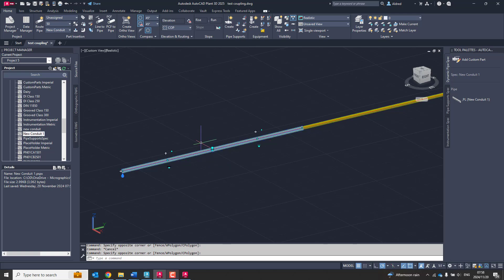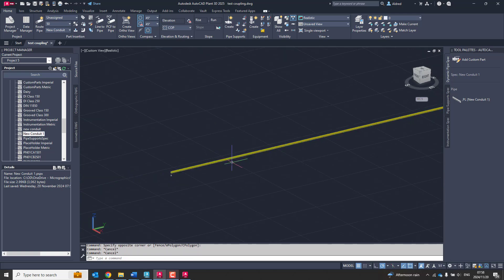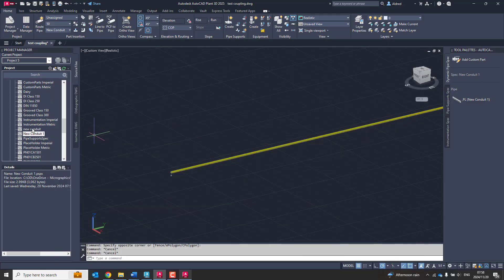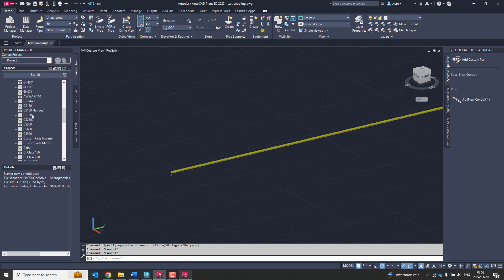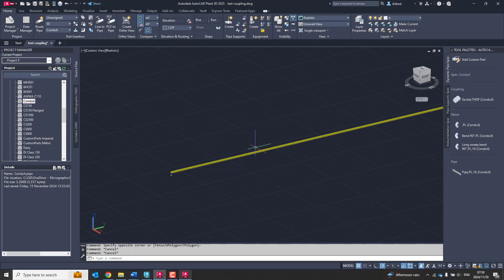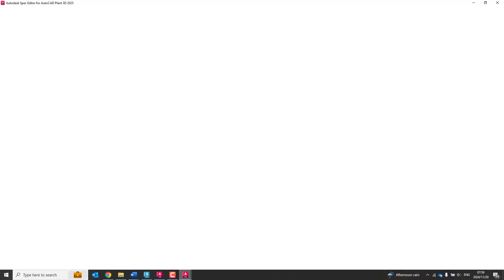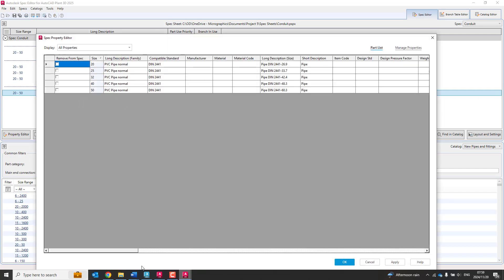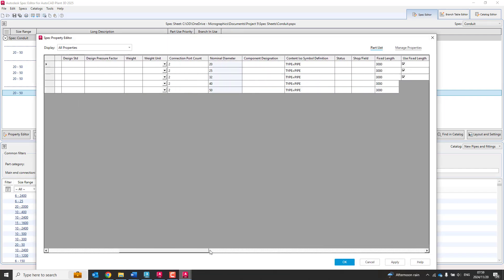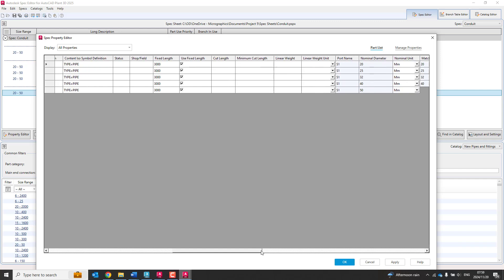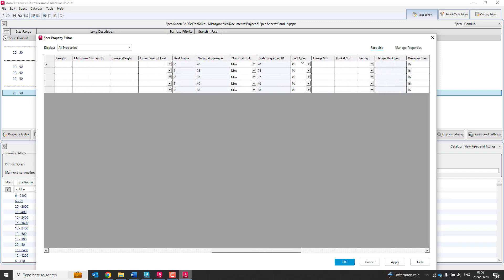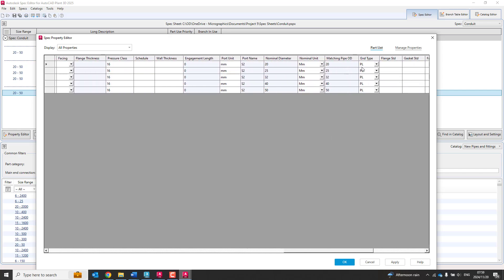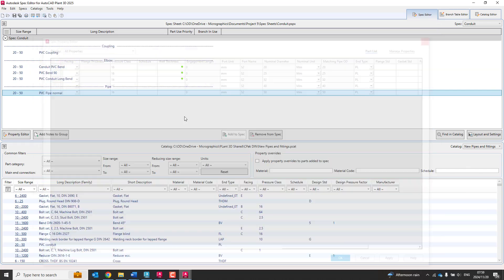Now what happens is I want to have a conduit in there. So with that, what we need to do is we need to go and find a conduit in our spec and catalog, which will match up with our pipe and then add it to the spec as well. So I've sort of preset this up, and if I go to my conduit over here, you'll notice I've just put in some more. So I've got the sockets, I've got some elbows, and I've got my pipe. Now if I go to edit this spec, you'll see with my pipe, I've got the 20 to 25, and you'll notice I've got a fixed length of 3,000 and use that fixed length as well. Now what you'll notice over here, this is the very important part, is the end-type is PL on both ports.